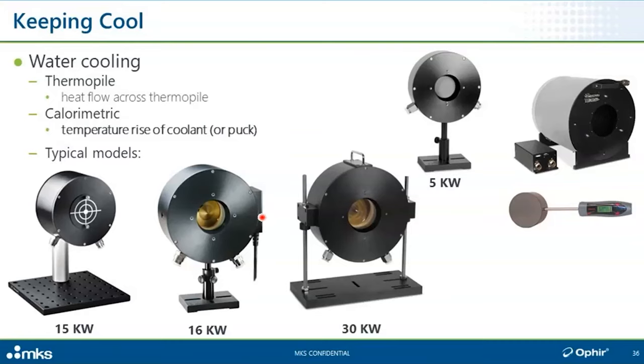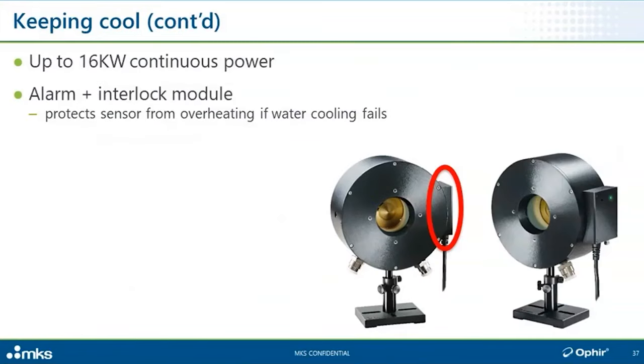I just want to say something about this 16 kilowatt sensor. We released this a couple of years back. I just want to point out this module over here. In about a minute or two, we're going to say something about cooling water. This is an alarm and interlock module. The user can hook this up and configure it so that if there's any failure in the cooling water system, it can automatically disable the laser to prevent overheating from damaging the sensor in case of such a failure of the cooling water system.